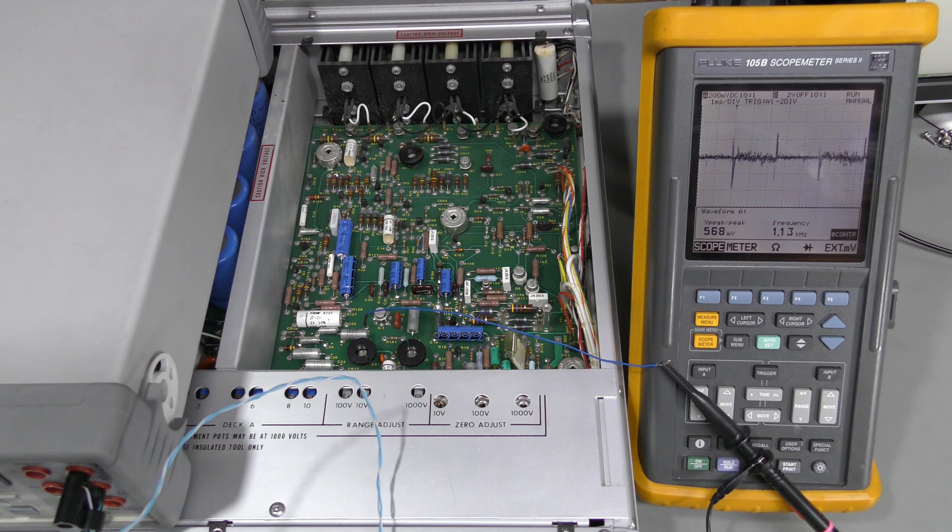The offset did not go away, so I started going through troubleshooting steps and I found that the chopper amplifier needed adjustment.